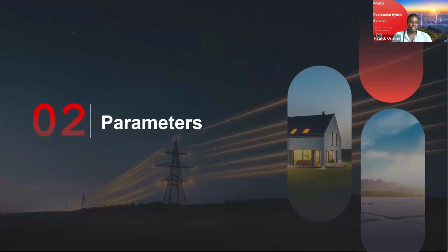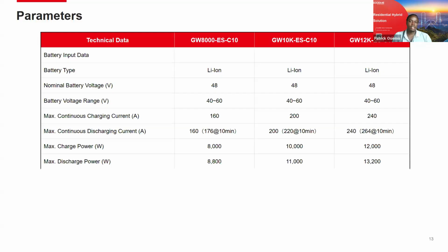The parameters of the ES Unique are quite unique in this sense. As you can see on the battery side, as I mentioned, we're able to charge up to 240 amps. The lowest, 8 kilowatt, outputs 160 amps, the 10 kilowatt outputs 200, and the 12 kilowatt outputs 240 amperes. The inverter is able to charge and discharge the battery at the inverter rating. So the 8 kilowatt can charge and discharge the battery at 8 kilowatt, similar to the 12 and the 10, depending on the inverter rating.